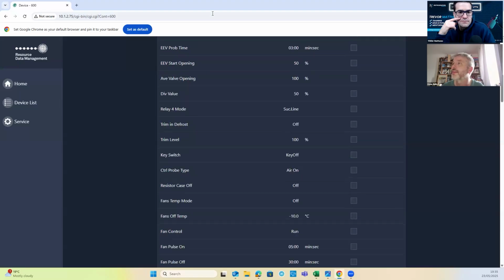Okay, so I won't go through every setting. Read the manual. There are thousands of settings across RDMs. I think it's important to read any manual, but for an example, start opening percentage. That's going to be different if you're on a chiller versus a long run cold storage. Because if you have that at 75% open start opening and you're only 2 feet away from the compressor, you're going to be in some trouble.